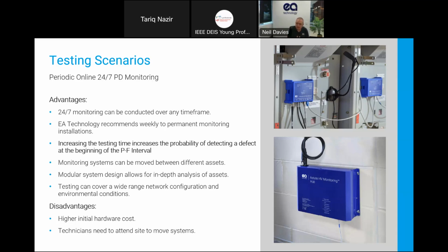Realistically, if you've got a very short P2F interval, say a P2F interval of 3 months, then choosing 1 week in a year versus 1 day in a year is not massively changing your probability of detecting that defect first. But what periodic monitoring, putting a monitor on for a week, does is allow you to test under a different set of network configurations. So pumps are switching in and out on a daily basis, or swapping configuration. You're seeing the loading on the network changing from the day to the nighttime. We've certainly seen defects which are affected by load.